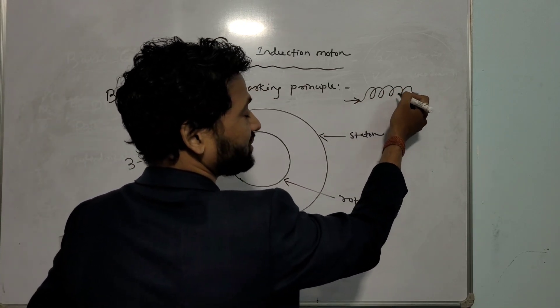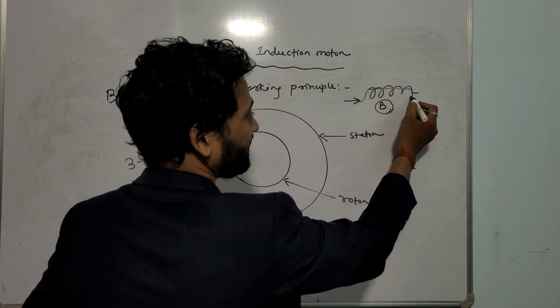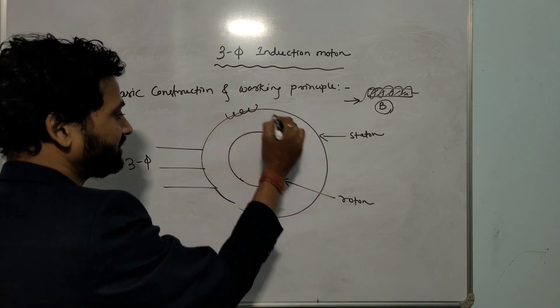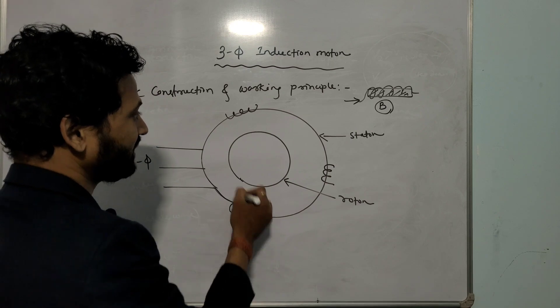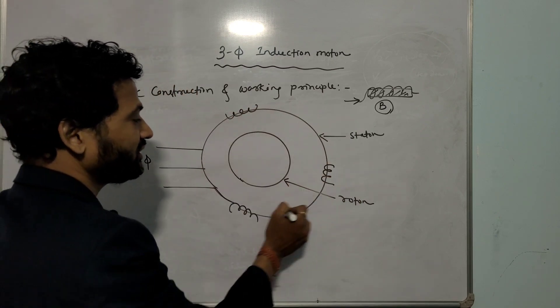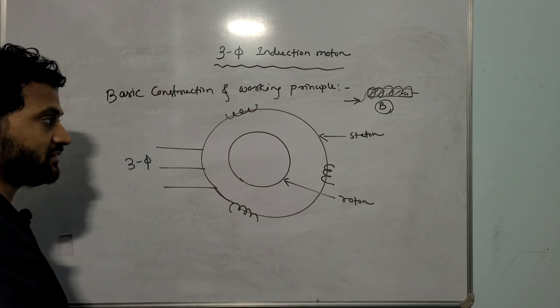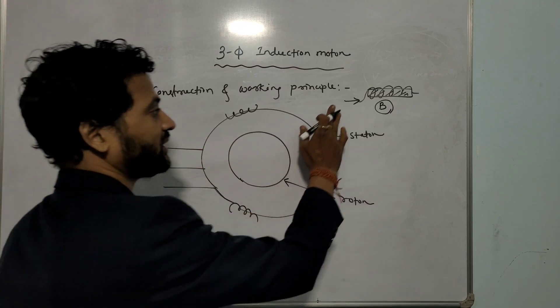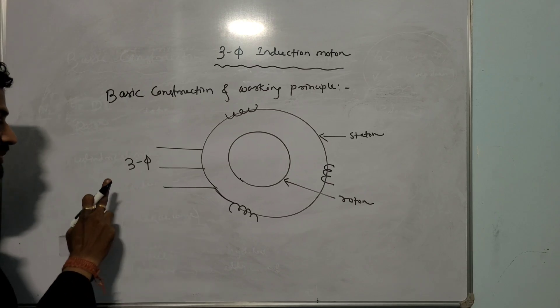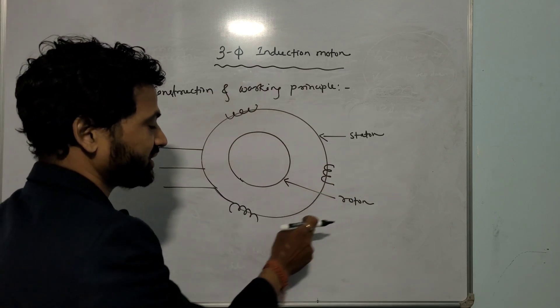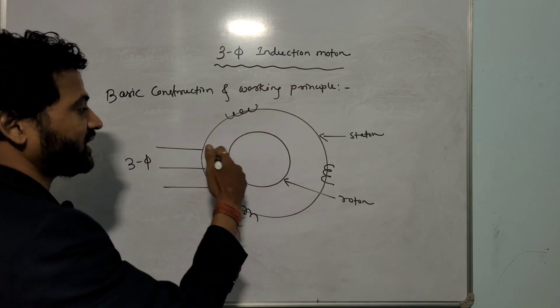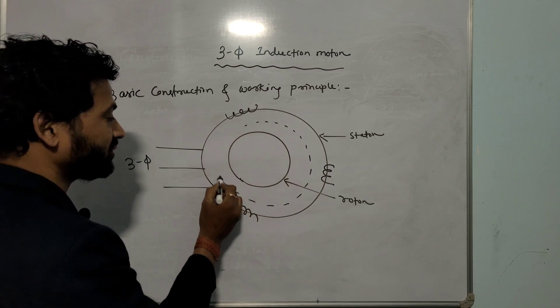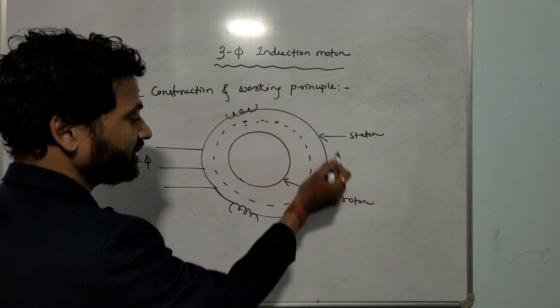Whenever current is given to a solenoid or coil, a magnetic field is developed — just like in Class 12 solenoid concepts. To strengthen that magnetic field, we can use a core. Similarly here, the three-phase winding has a 120-degree angular difference between consecutive coils, with a soft iron core made of silicon steel. The entire system will produce a magnetic field whenever energized from the 3-phase supply. When 3-phase supply is given to the stator winding, it will be energized and produce a magnetic field.